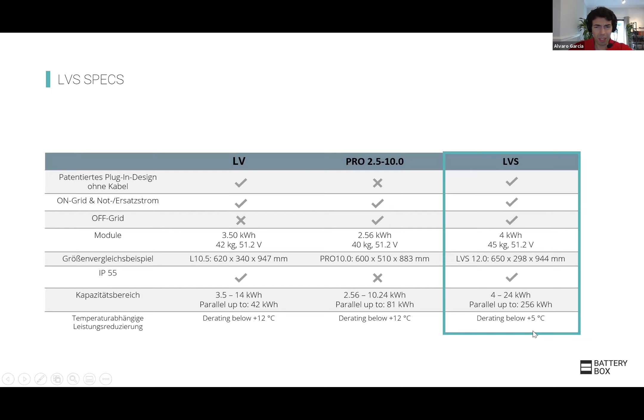One of the first things that are slightly different between the high voltage and the low voltage is, as you can have so many modules in parallel, we prefer to offer you the possibility of having the communication module outside. That's the BMU. So you just need one BMU per system. You can have 64 batteries with just one BMU. And this is the one that would be interfacing with the inverter.